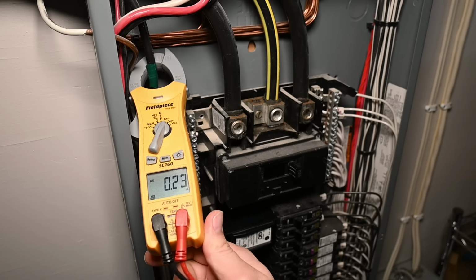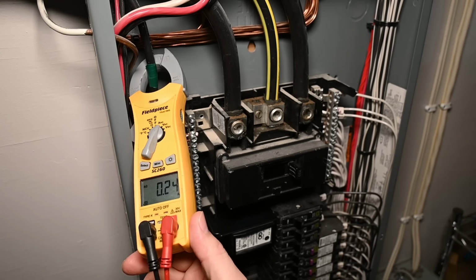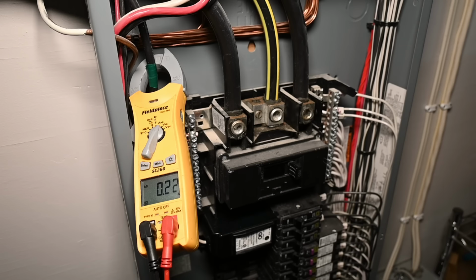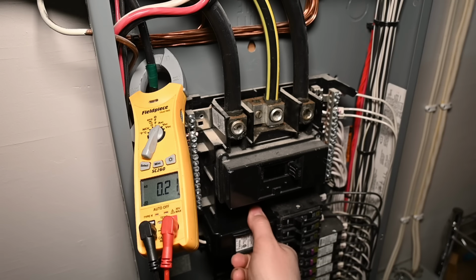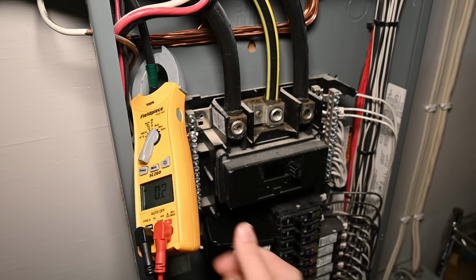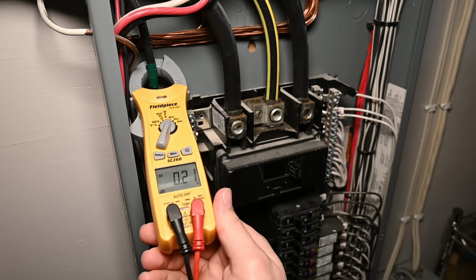So you guys can see that our amp draw has gone up to 0.24, 0.22 now. So I'm just going to pop this surge breaker out here and see if that has anything to do with what's going on. Very carefully. That did not change it at all either.